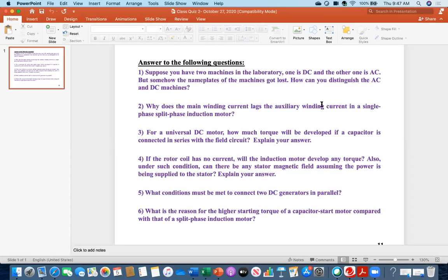So mainly you will be telling two points: when the nameplate information is lost, by looking externally — if there are three terminals, that is definitely AC. If there are two terminals, it can be DC or AC. To confirm, look internally: if you see a capacitor, that is single-phase AC; otherwise, that is DC.